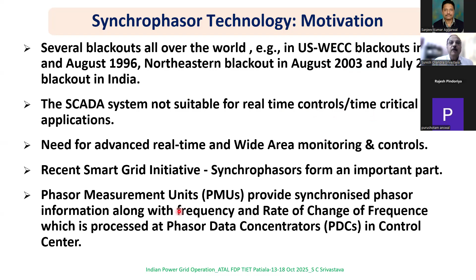Our committee gave the recommendation for this because the SCADA system is not suitable for real-time controls, it only gives magnitude information, so you get voltage magnitude and current magnitude, but you don't get phasor information, which is critical for stability monitoring and angle monitoring. Wide area monitoring and control is also required, and you need a faster monitoring system. The SCADA system's scan rate is about 4 to 10 seconds, because every RTU is polled and then the data comes back.